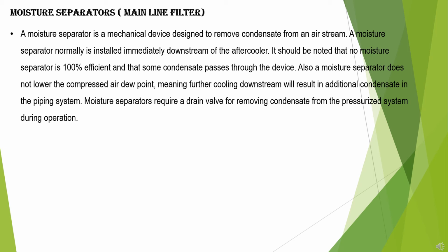Also, a moisture separator does not lower the compressed air dew point, meaning further cooling downstream will result in additional condensate in the piping system. Moisture separators require a drain valve for removing condensate from the pressurized system during operation.